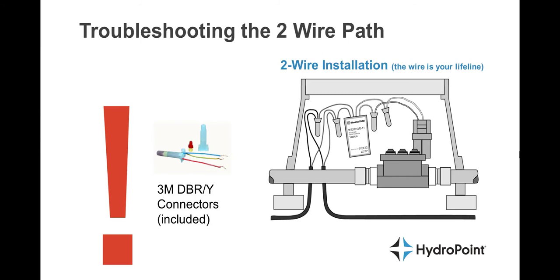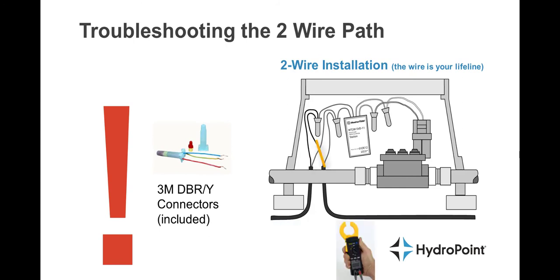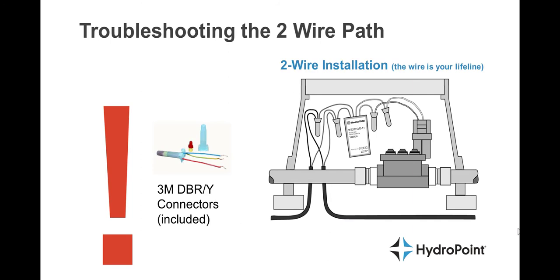In the field test you are following the 2-Wire path that starts at the bottom of the valve box, comes into the valve box where there are two wires going in, runs through the decoder and the valve, and then runs out of the valve box. So in every valve box I want four measurements: line one coming in and going out, and line two coming in and going out. Literally take your clamp meter and wrap it around line one on the in-line, then line one on the out-line, then line two on the in-line, and line two on the out-line.